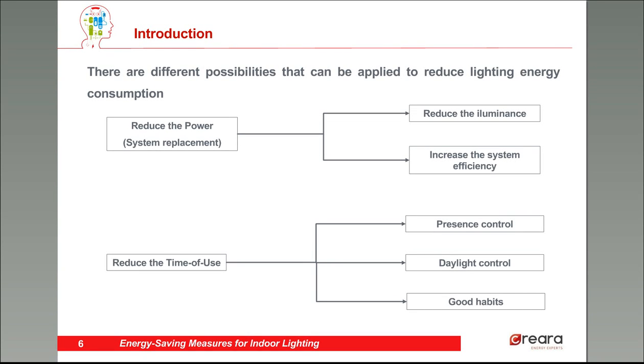For decreasing the power, the first option is to analyze the lighting level, the illuminance. If the illuminance is too high, an energy saving measure would be to reduce it. If the illuminance is correct or even sometimes low, there is no saving here. But we can always improve the system efficiency — we can improve the luminaire, the lamp, or even the auxiliary equipment. Right now, with the lighting revolution produced by LEDs, almost every luminaire can be substituted with a more efficient system. We just have to analyze if this change is interesting from an energy, economics, and even environmental point of view.